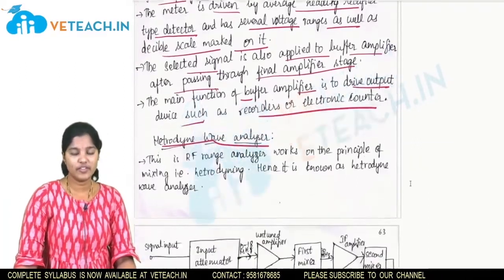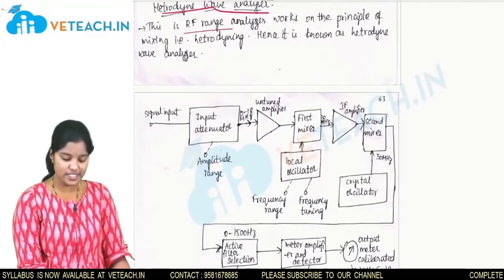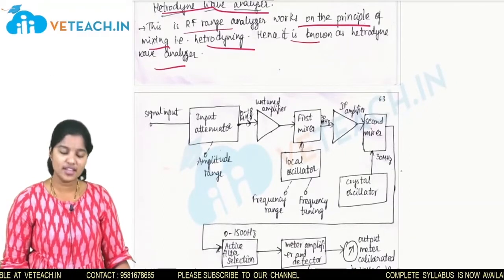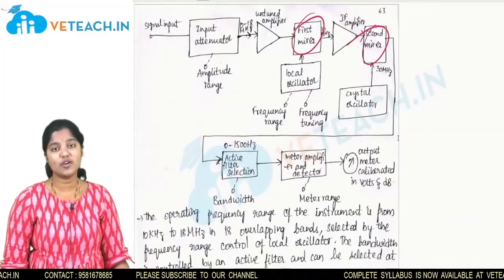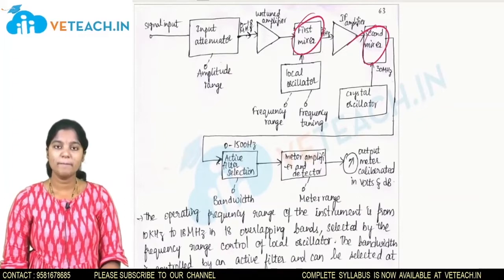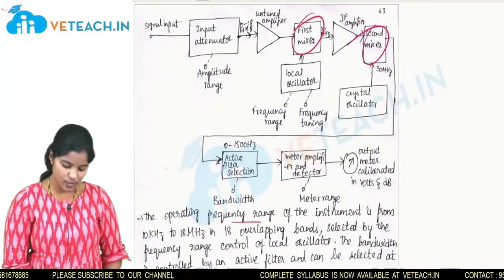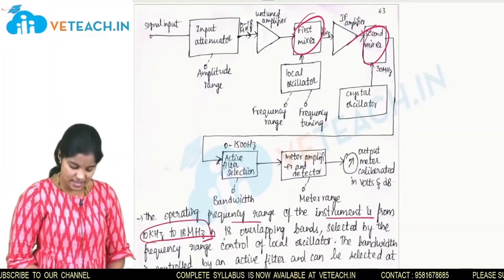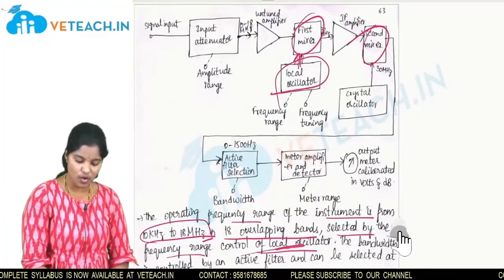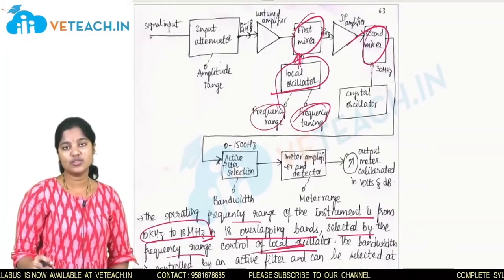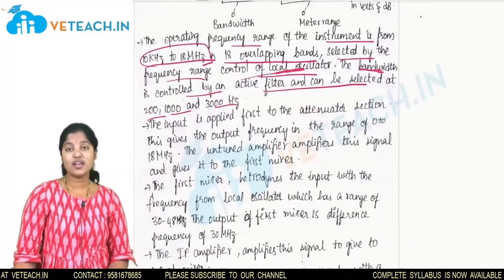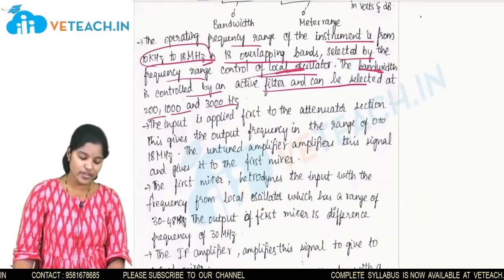The second type is the heterodyne wave analyzer, which is an RF range analyzer. It works on the principle of mixing, that is heterodyning the signal — hence it is known as a heterodyne wave analyzer. It has a first mixer and a second mixer. The operating frequency range is from 10 kHz to 18 MHz, in 18 overlapping bands selected by the frequency range control of the local oscillator. The bandwidth is controlled by an active filter and can be selected as 200 Hz, 1000 Hz, or 3000 Hz.